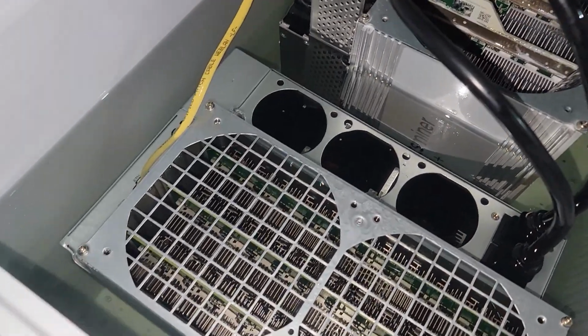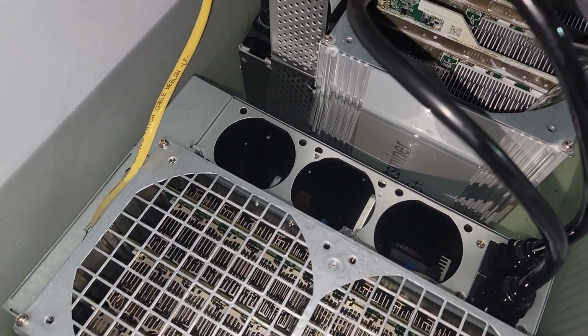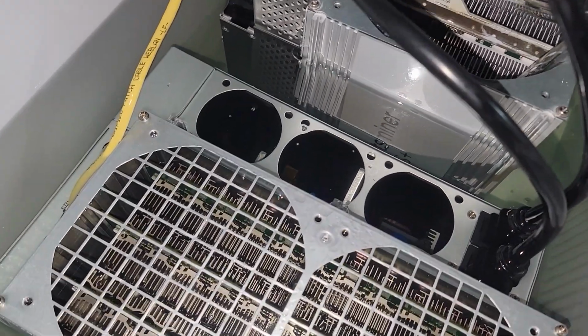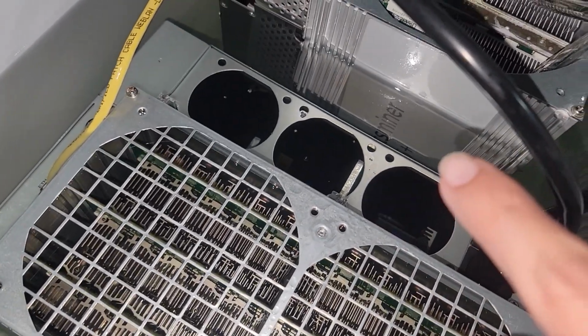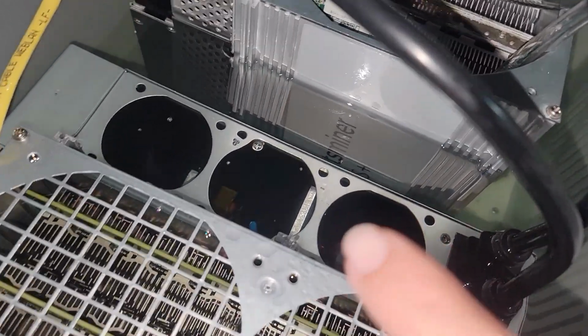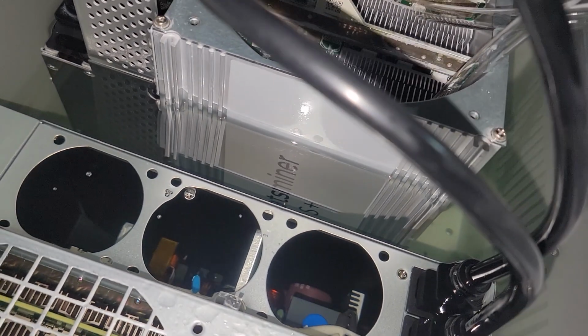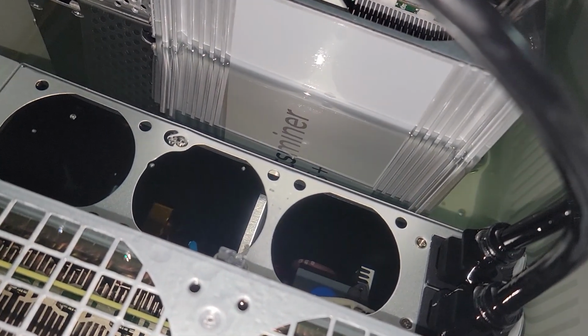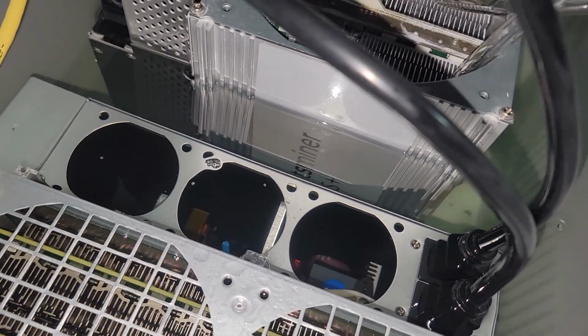This is why I mentioned setting your miners in there before you fill it with liquid, because originally, before the S19K Pro was sitting there, we were right below the R on the Whatsminer, and now we're about a little bit over a half inch, maybe 3/4 of an inch higher, not too far from the overflow.